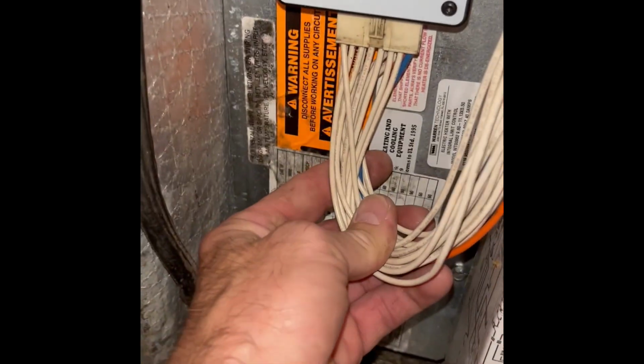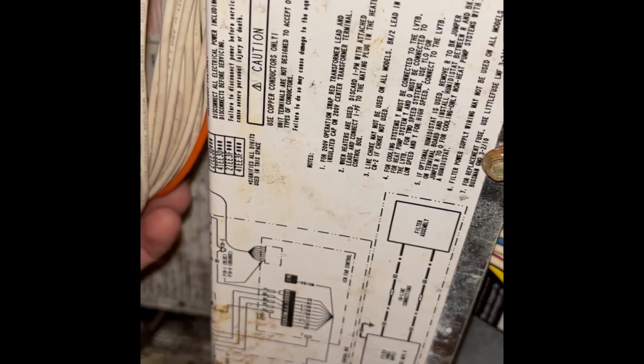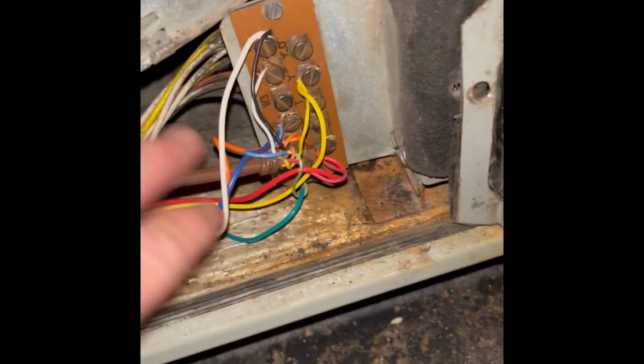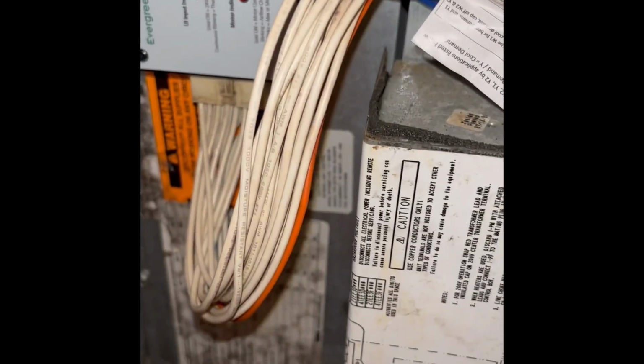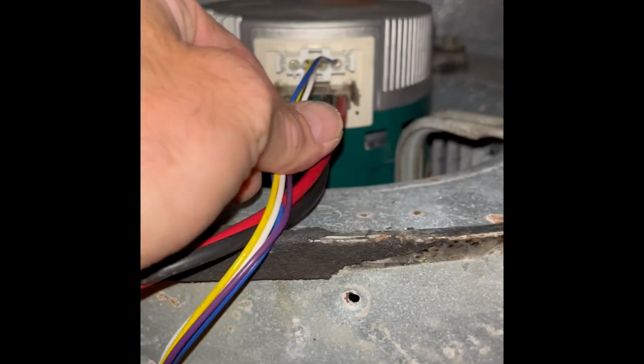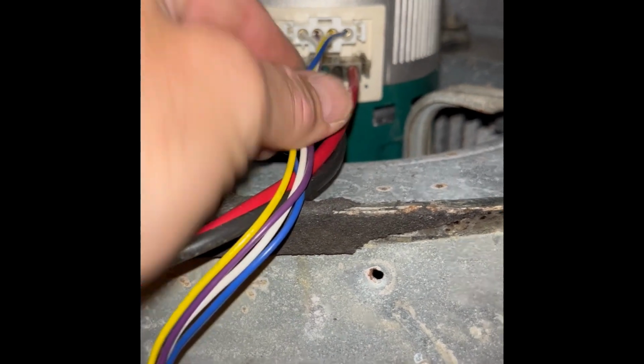So to wire it, we're going to take the 16-pin connector directly from our onboard controller from the unit, connected to our interface, and then we have our low voltage wires behind here. We're going to bring them down and connect them to all of our other low voltage thermostat wires. Basically, the instruction manual will tell you exactly how to do it. It's pretty easy. Then we're going to take our interface wires and come up to our 4-pin connector to our motor.